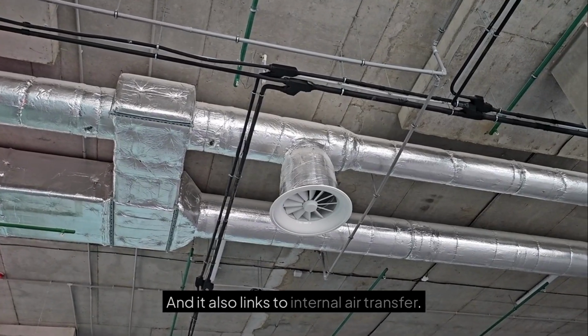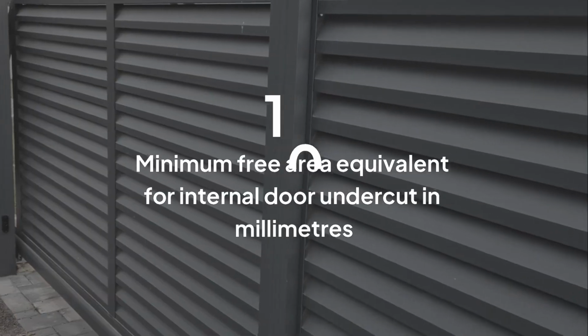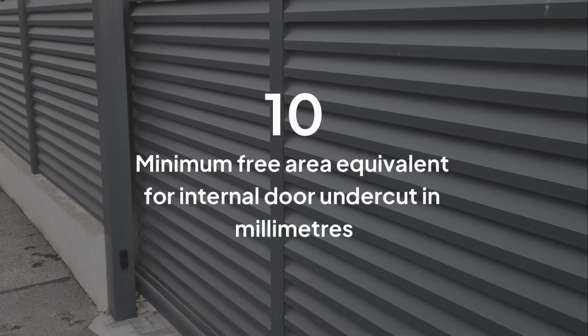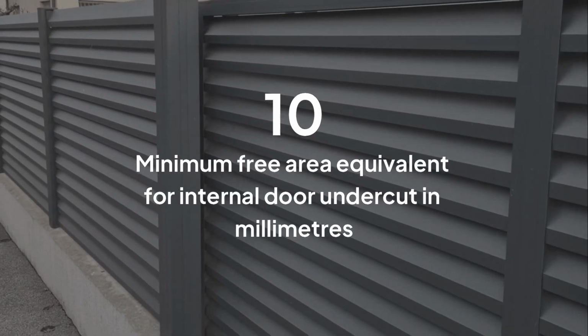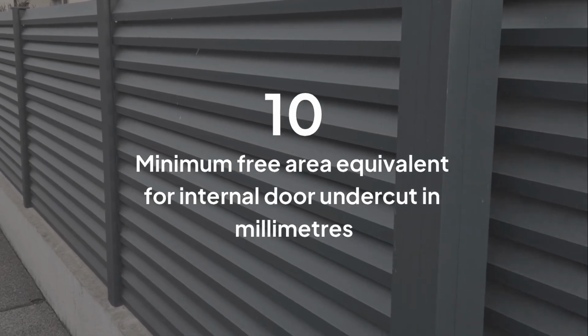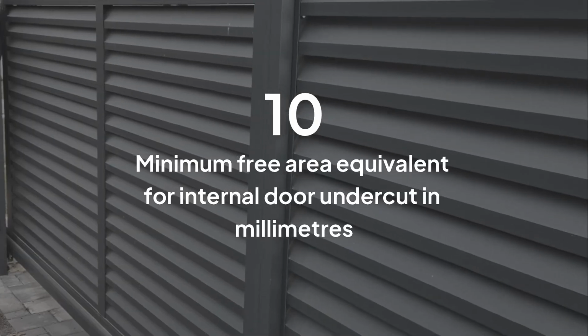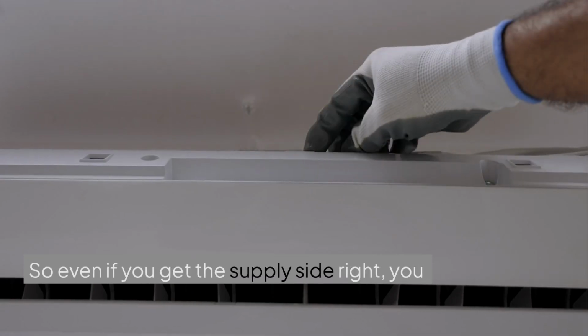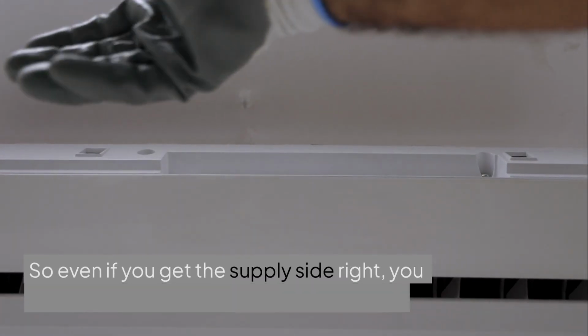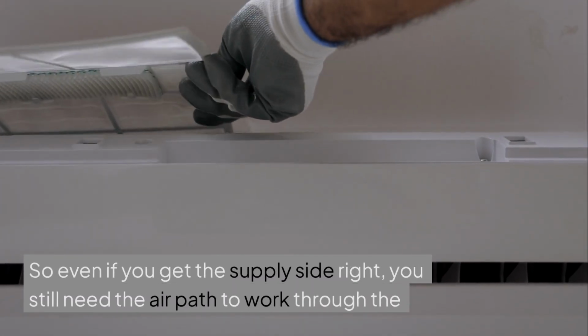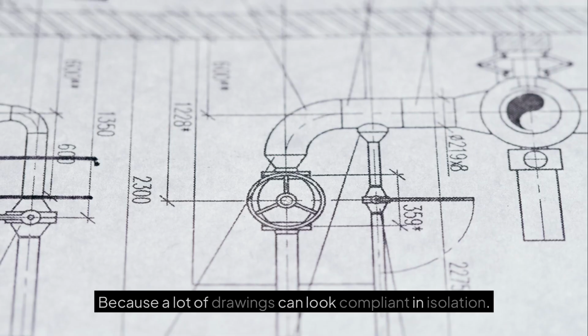And it also links to internal air transfer. Paragraph 1.21 says internal doors should allow air to flow through the dwelling by providing a minimum free area equivalent to a 10 mm undercut in a 760 mm wide door. So even if you get the supply side right, you still need the air path to work through the home. That is a really important design mindset.